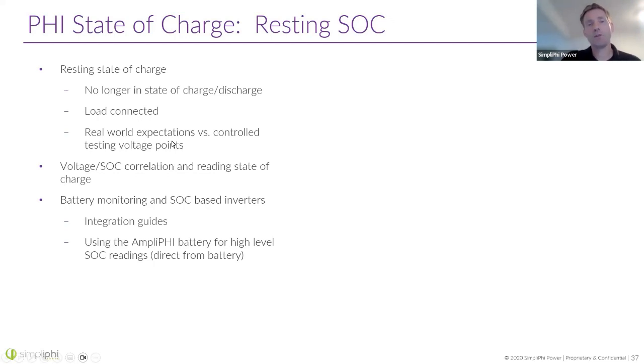And so we'll look at the voltage versus the state of charge. It really depends: if your battery is really resting, it's easy to determine the state of charge of the battery based off the voltage. But if the battery is not resting, then it's a somewhat complicated calculation that the inverter needs to do. And for that reason, the state of charge monitors can often be off a bit. So you can find examples for programming and battery monitoring in our integration guides.